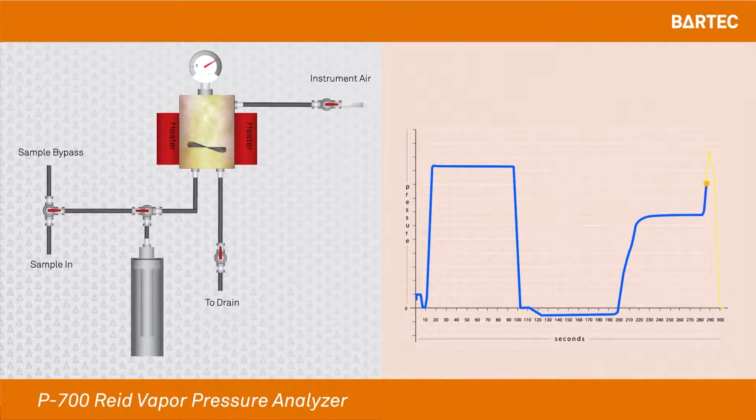Once the sample is loaded, we start the agitation to release the vapors of the sample and reach the RVP. Once the RVP is reached, it is recorded by the pressure gauge and the electronics and the cycle is finished. We purge the measurement cell and get ready for the following analysis.